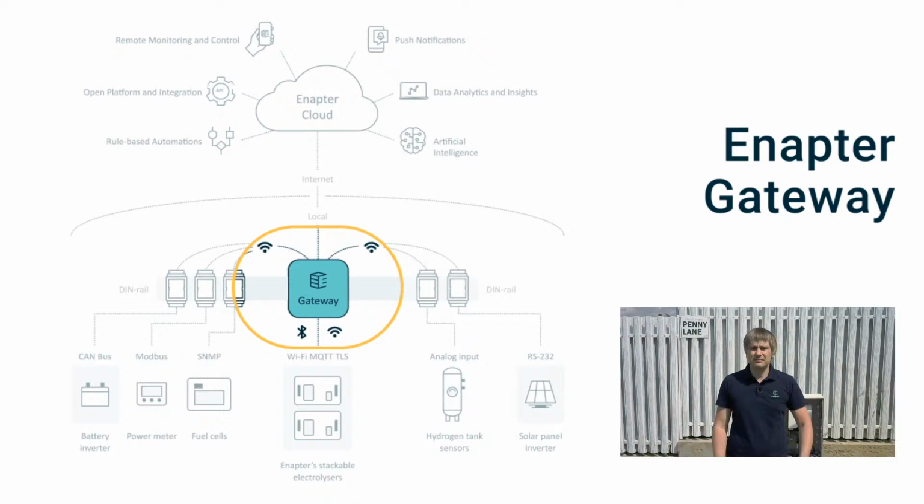The second component of our software setup is open source gateway, which is based on Linux operation system. It runs on a standard Intel-based hardware, and in my case, I use Intel NUC platform. You can see it on the DIN rail in the cabinet behind me. The role of this device is to aggregate the data from all universal communication modules on site and control logic of energy systems with rule-based engine.